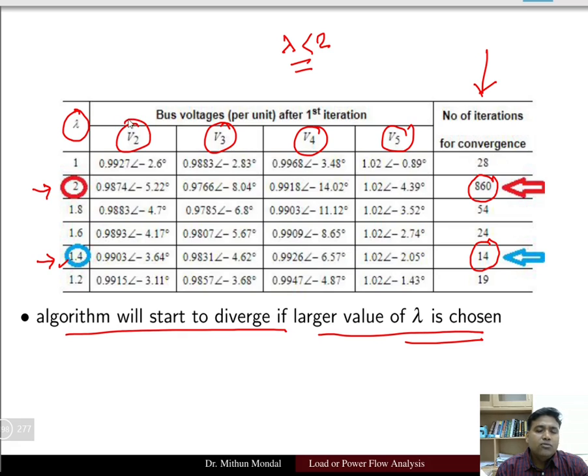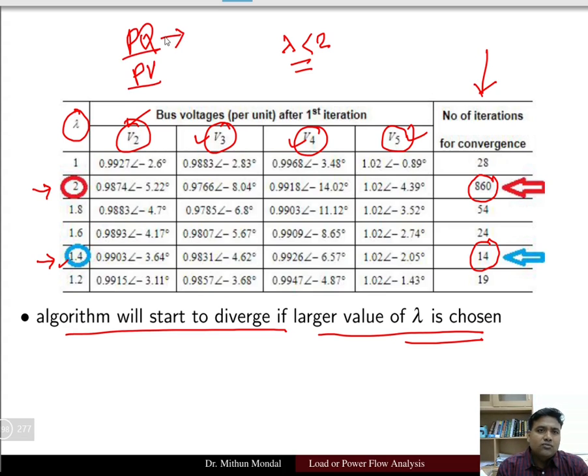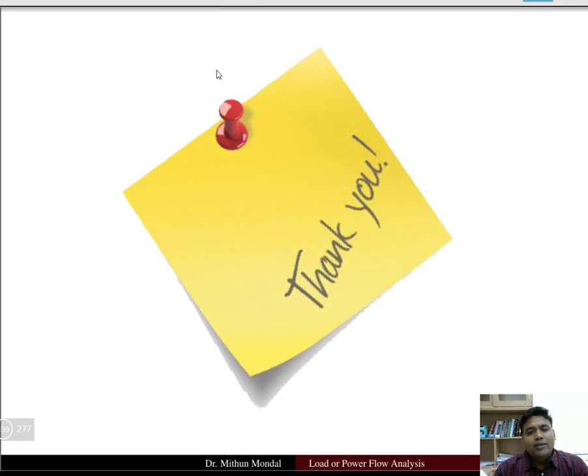To summarize the Gauss-Seidel load flow algorithm: first update all PQ (load) bus voltages, then update the PV (generator) bus voltages. Check Q limit violations for generator buses. The process terminates when all power mismatches are below the specified tolerance. This completes the Gauss-Seidel method; in the next class we will cover the Newton-Raphson method.